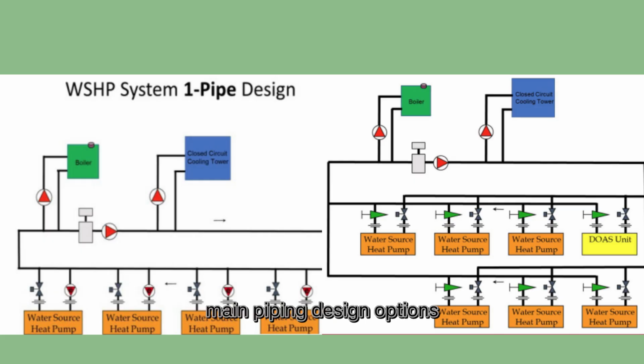Let's go over the main piping design options used in WSHP systems. First, the one-pipe WSHP system. In this setup, each heat pump has its own circulator pump, which moves water through the common loop. It requires fewer valves and has a shorter installation time, making it cost-effective and simple to build. This design works best for smaller buildings, such as schools or low-rise offices.